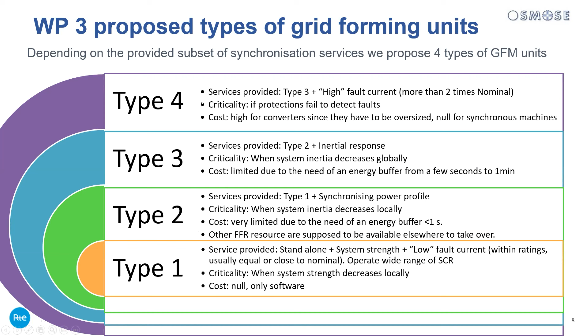Then you have type 3, where you provide, on top of type 2, inertia response. Therefore, you need a bigger amount of storage, a few seconds, maybe a few tens of seconds. And then you have type 4, when you do type 3 plus very high fault current, more than 2 times nominal current.